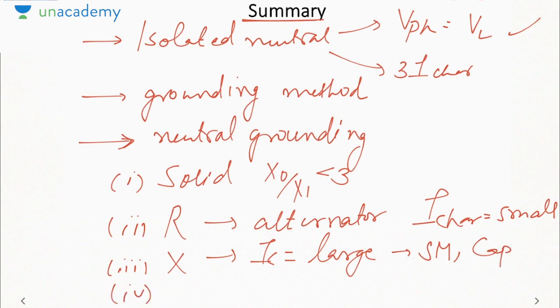Then we saw the arc suppressor coil or the Petersen coil, which was 1 by 3 omega square C, which will completely suppress the arc as it will cancel the line charging current. So these are the following methods of the neutral grounding. In the next lecture, we will consider the problems based on unsymmetrical faults and understand how to analyze the unsymmetrical faults. That will be done in the next lecture.